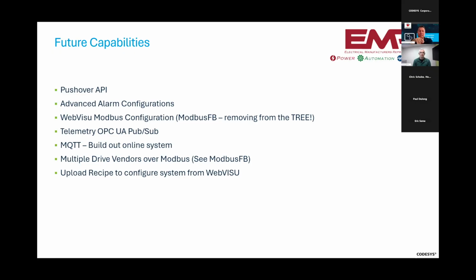And then the last is being able to upload the recipes directly from the WebVisU. So opening a file window so that we can suck in the recipe directly from our Chrome or our web interface. And then the multi-vendors on the Modbus, we want you to be able to drop down and say, I've got an ABB drive on VFD1. I've got a Yaskawa on VFD2, and mix and match however you want. Because with the Modbus function block, you're able to do that at runtime. So we can change all of those, what it's reading to, what it's writing to, through runtime once we get that implemented.